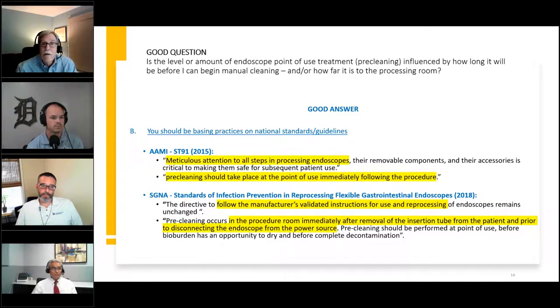Processing staff need to follow manufacturer prescribed steps for delayed processing in those circumstances where the manufacturer's recommended time between point of use treatment and manual cleaning is exceeded.